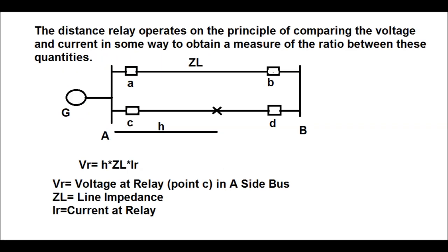The distance relay operates on the principle of comparing the voltage and current in some way to obtain a measure of the ratio between these quantities in terms of impedance. In this figure, two substations have been shown. The line impedance is shown by ZL. A fault occurs at a distance of a fraction H of the line. Vr is the voltage seen at relay point C of bus A, equal to H × ZL × IR. IR is the current at the relay, ZL is the line impedance, and Vr is the voltage at relay point C on the A side of the bus.